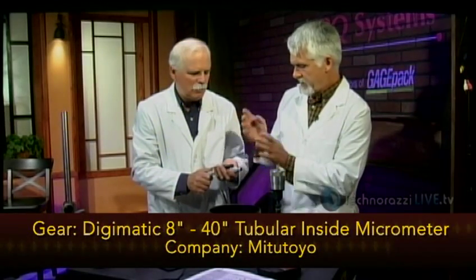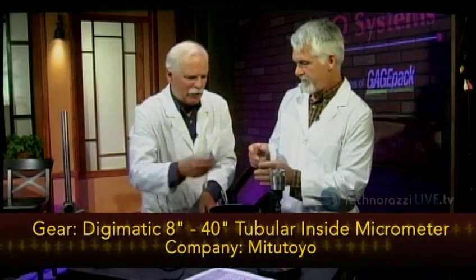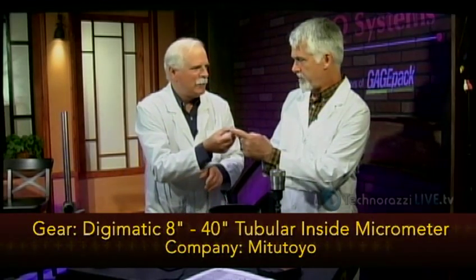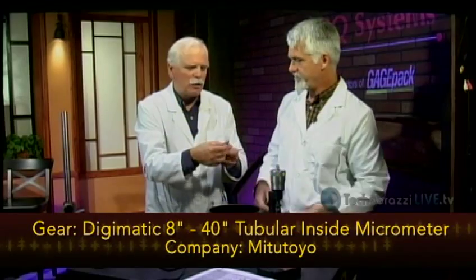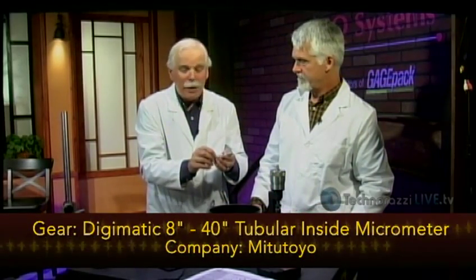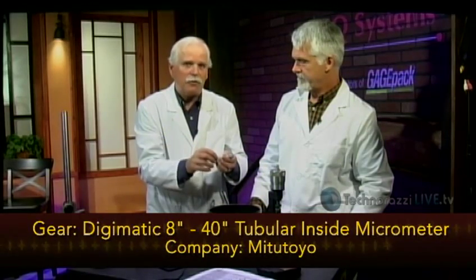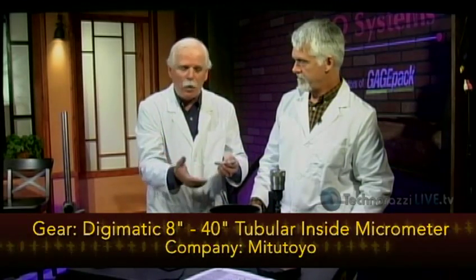They don't move. So you're saying some people will take one of these, they'll usually be using one of those, and they'll measure it with an OD mic because they don't trust the reading. Before they've been calibrated, I can understand that. But after they've been calibrated, all you're doing is throwing in the tolerance of the OD mic with the tolerance of the ID mic. You've just doubled your tolerance.